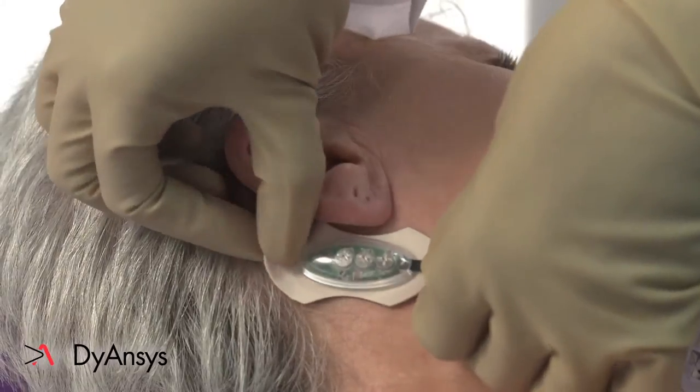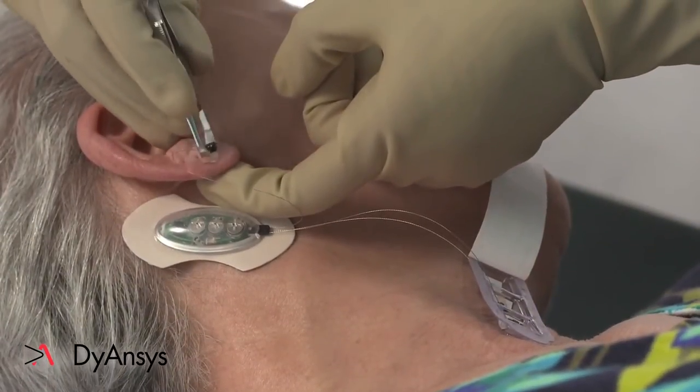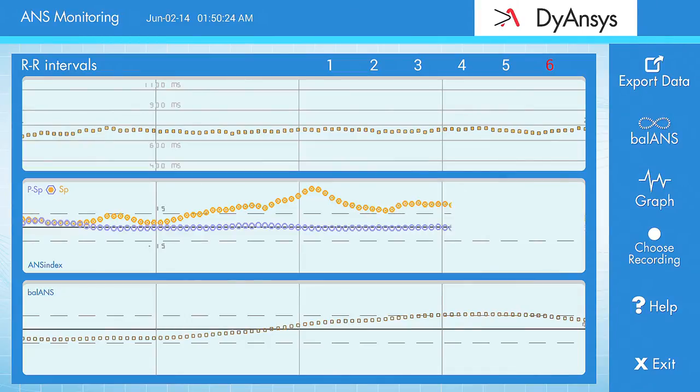Attach the ANSiStim control module with adhesive behind the patient's ear. Use the ANS monitoring function on the ANSiscope to monitor the patient's autonomic response to needle placement. The sympathetic response should rise after needle insertion, but drop close to the original value after several seconds.